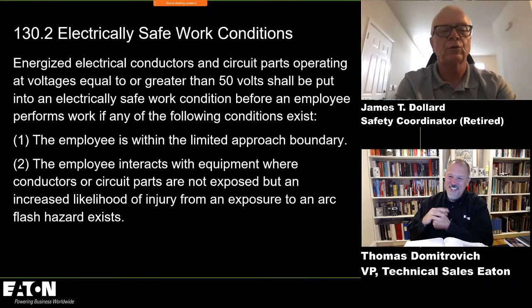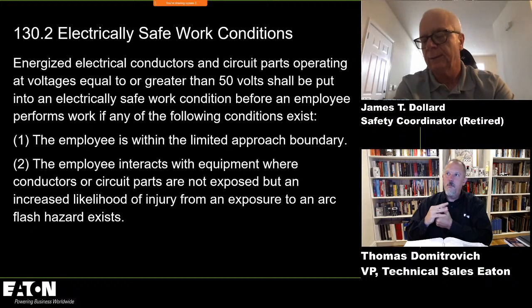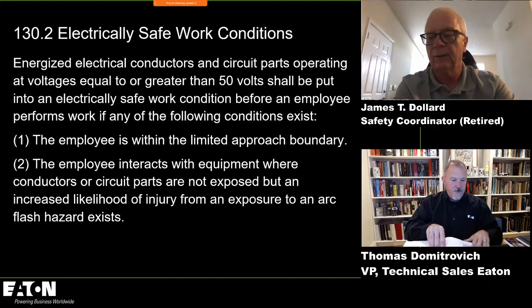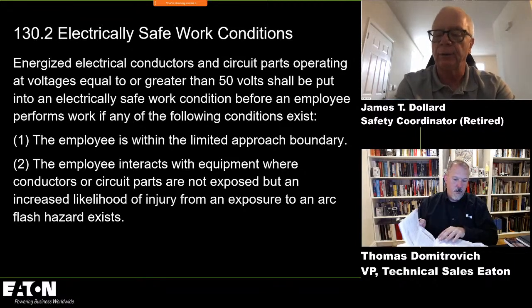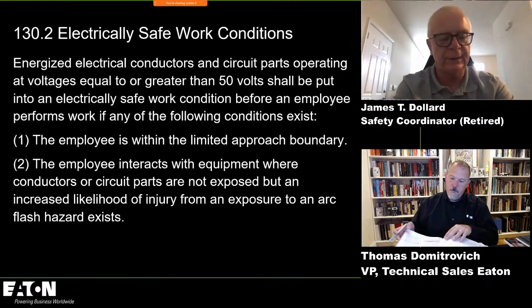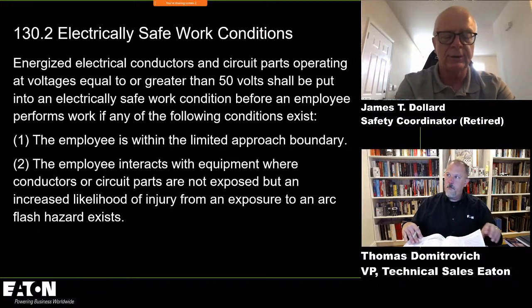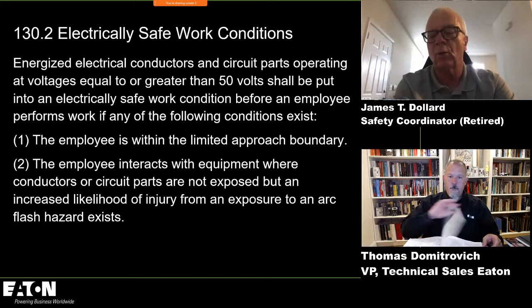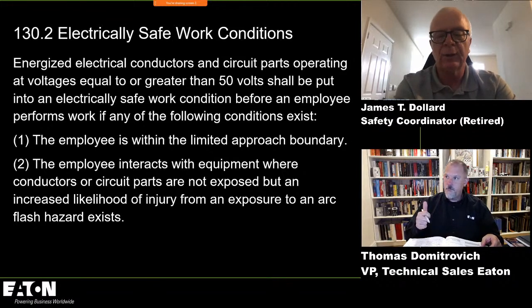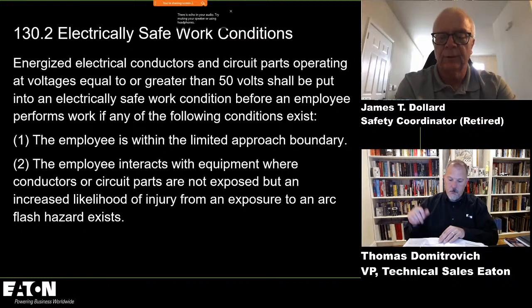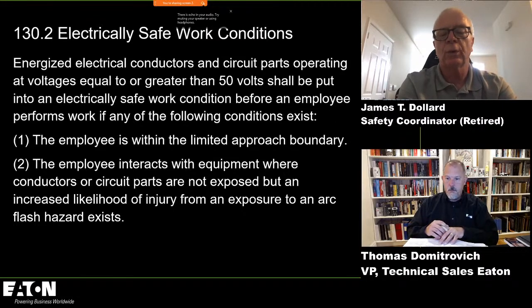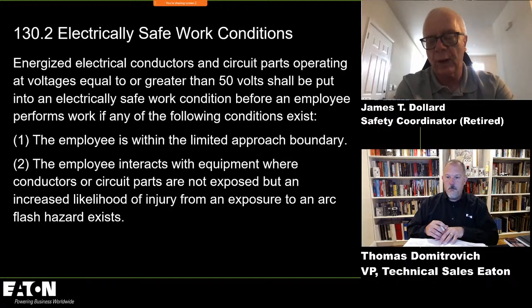But what's on the screen here, and I'm glad you threw this in there: Article 120 gets into electrically safe work conditions. When we are up front doing our risk assessment in 110.1(H) and NFPA 70E, and we take a look at the hierarchy of risk control, list item number 1 is elimination. The only way we can eliminate an electrical hazard from electrical equipment is to create an electrically safe work condition. And what you have here in 130.2 is the requirement for when you need to create an electrically safe work condition.